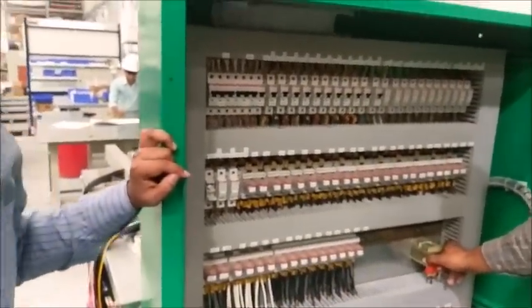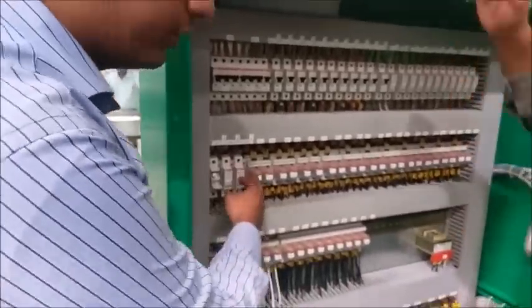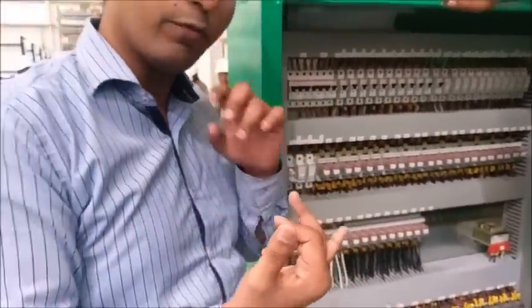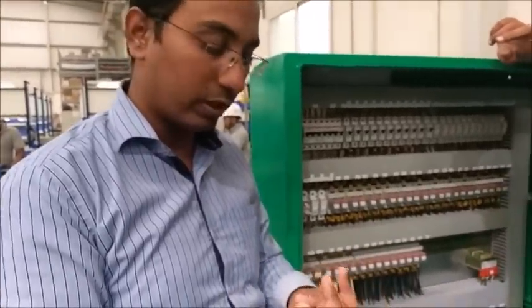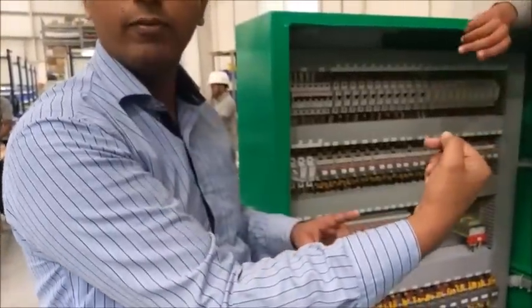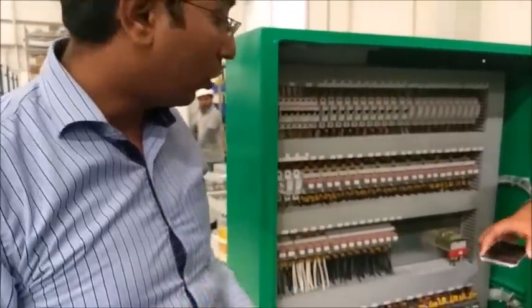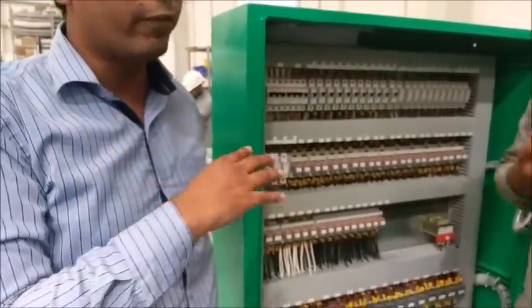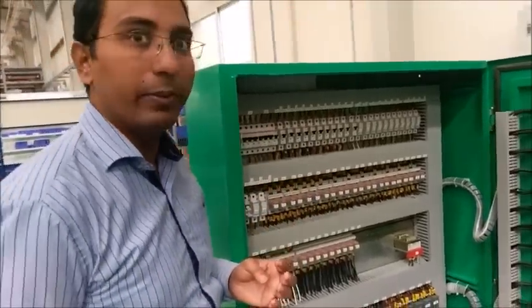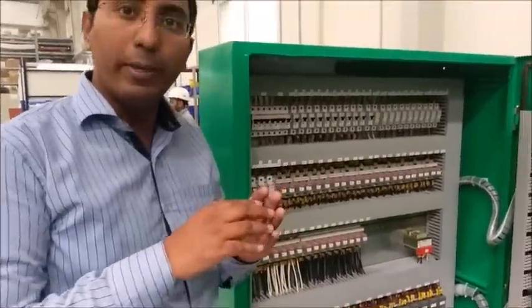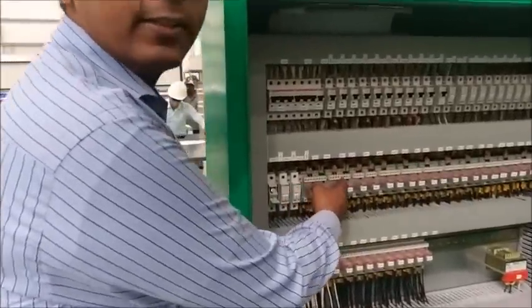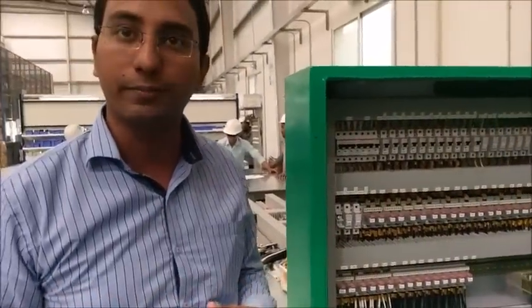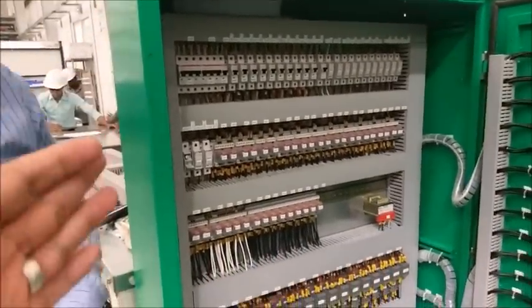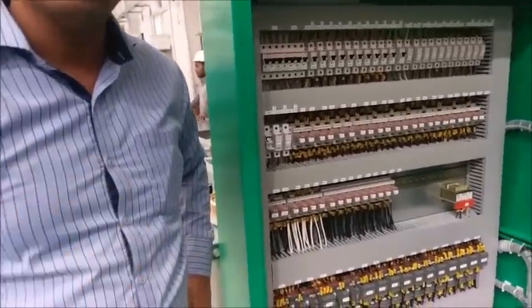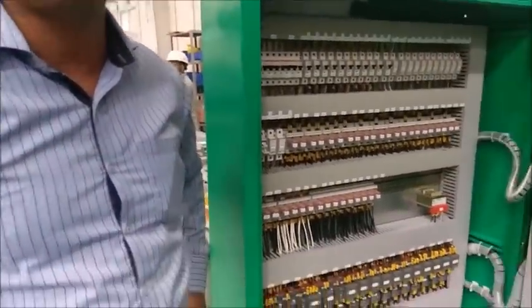This is again for the transformer. Sorry, what is he asking? We have to consider fire alarm, override, BMS, and panel manual on/off. So there are 4 commands, but in reality we have only one command. The voltage will mix, this supply will mix, so to make multiple commands we have to use relays. So this is multiplying the command. Once it takes the order, it gives an instruction in four different ways.